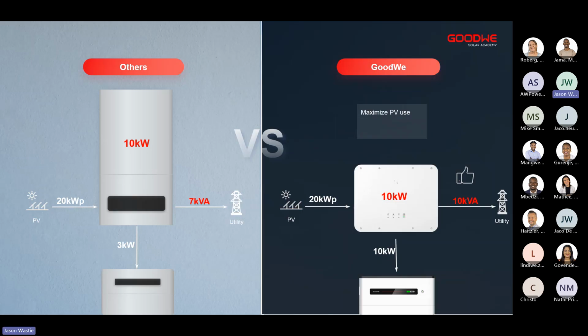PV oversizing. Our Goodwe inverters allow for PV oversizing, meaning that we can better use PV DC power excess after converting the inverter's capacity to AC power. As you can see in the slide, it demonstrates what I mean. We receive 20 kilowatts of DC power from the panels to the inverter. 10 kVA will output as AC power. The remaining 10 kilowatts will be used to charge the batteries DC.